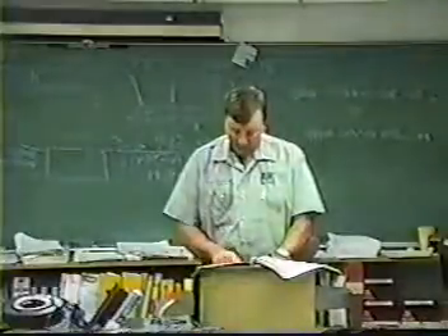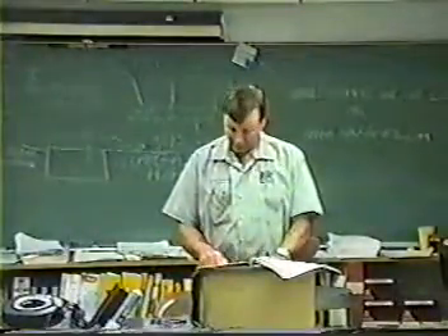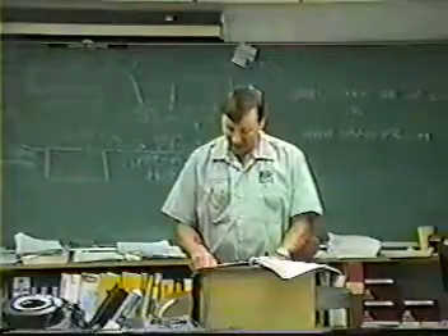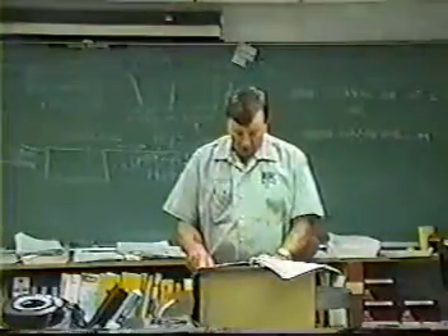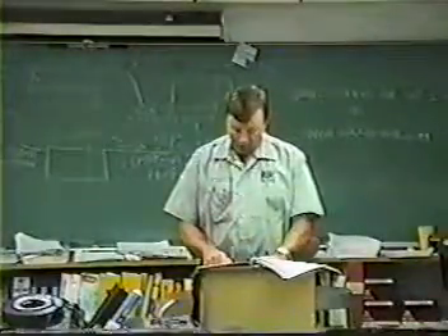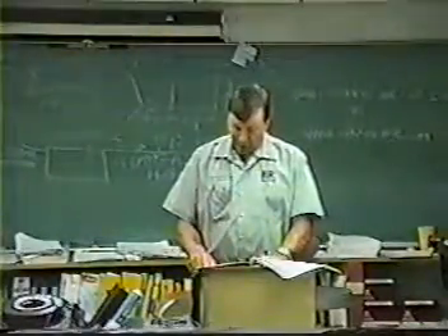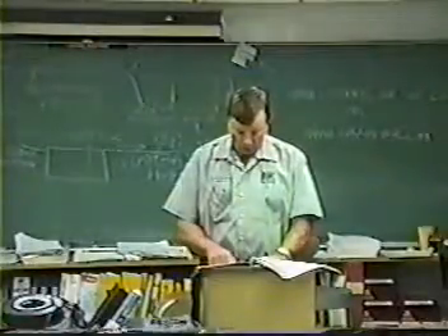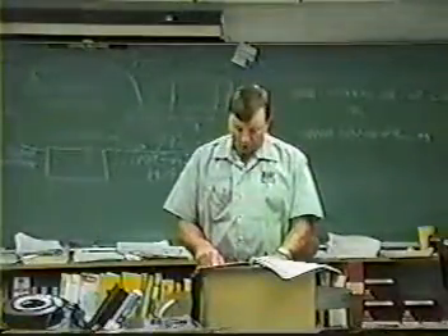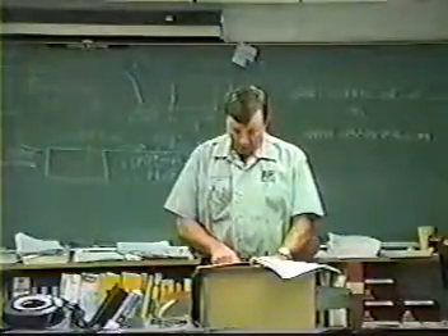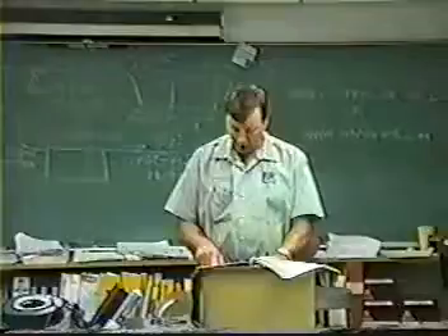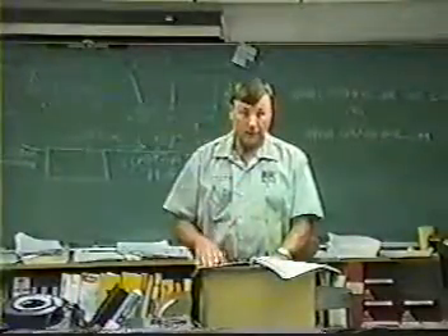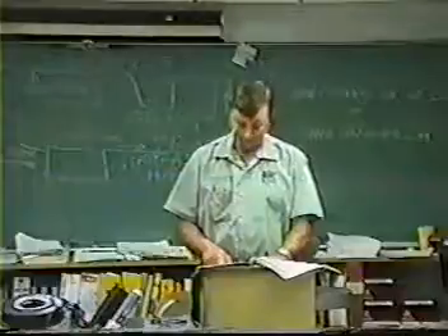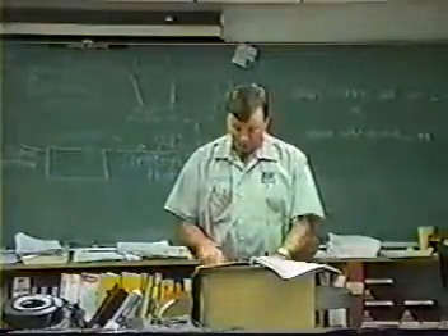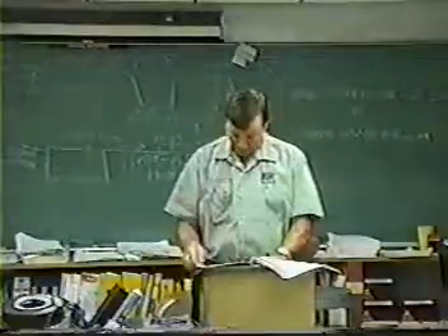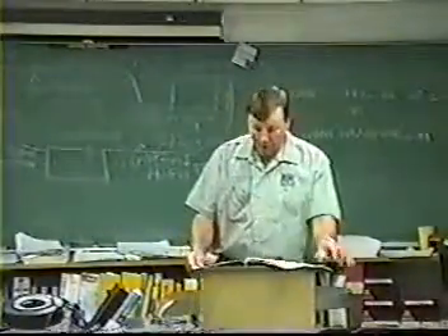ASHRAE Standard 15 requires all equipment rooms containing equipment utilizing an A1 refrigerant, R11, R12, or R134, must be fitted with an oxygen deprivation sensor and alarm. Equipment rooms with equipment using B1 refrigerant, which is R123, must be fitted with a refrigerant sensor. Never energize a reciprocating compressor if the discharge valve is closed. You'll blow that compressor up, you'll pop the reed valve in, or you could blow it up. So you make sure those valves are open before you go and energize that compressor if it's got valves on it. Okay, that's just a quick review of the core.